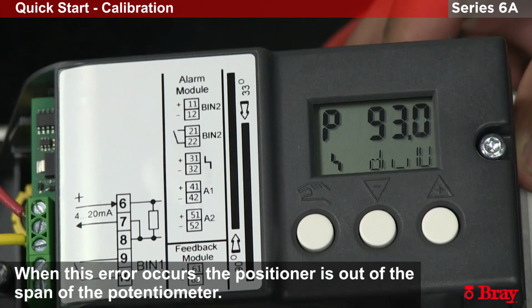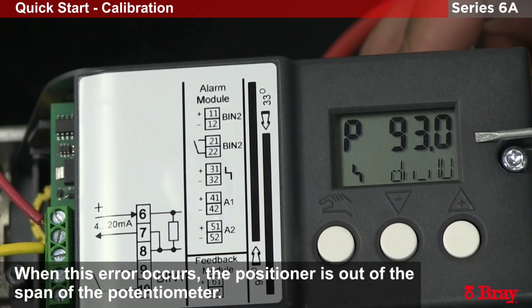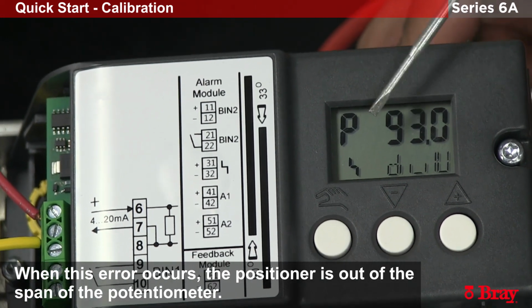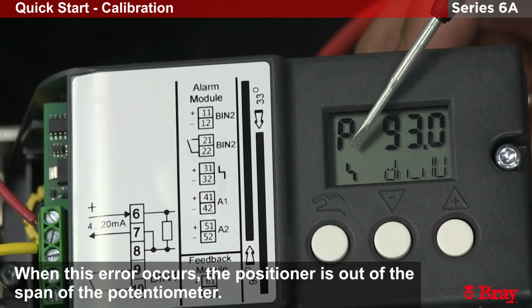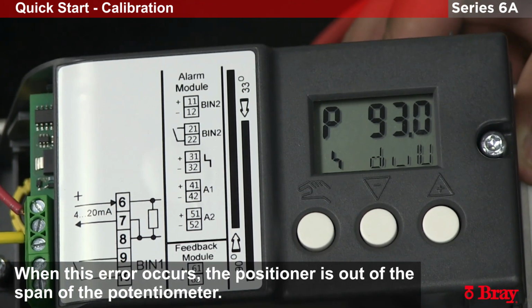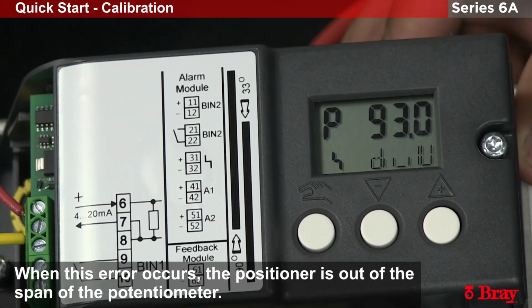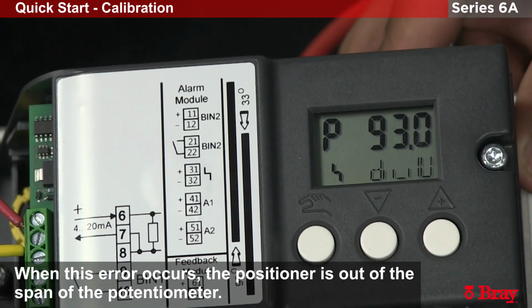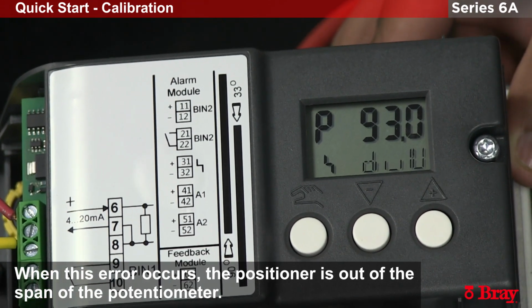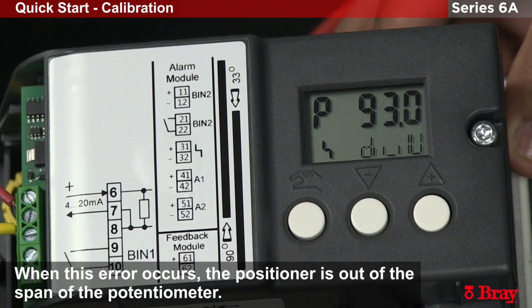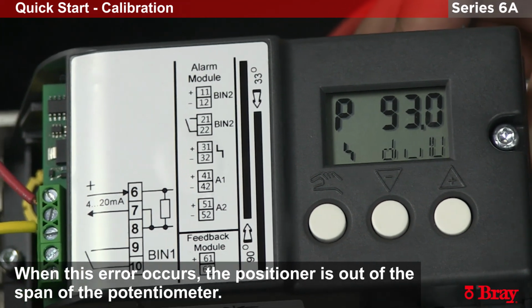During your auto calibration, you can encounter this error. We know we're in an error code because you get a squiggly line in the bottom left, indicating an error has happened. When this happens during calibration, it means we have come out of the span of the potentiometer.